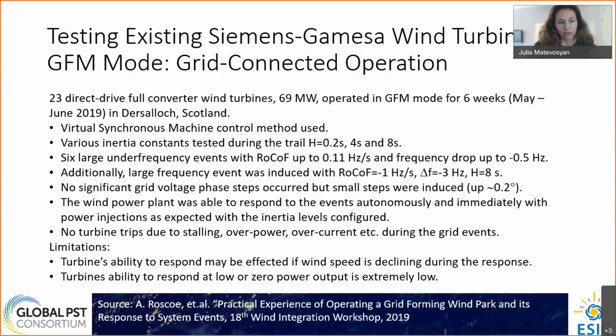Limitations that have been reported, and that's understandable, is that the wind turbines' ability to respond will be affected by wind speed declining during response. So, for example, if you have an under frequency event and the wind turbine is providing virtual inertia response, it may be affected if during the same time wind speed is decreasing. And then the wind turbine's ability to respond at low or zero power output is extremely low, since rotational speed is lower.